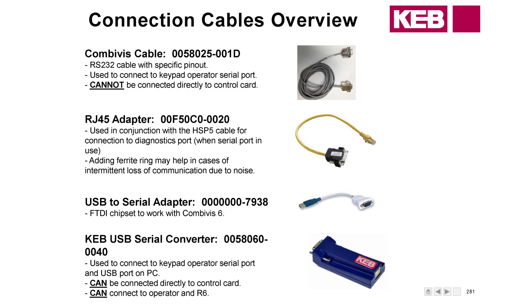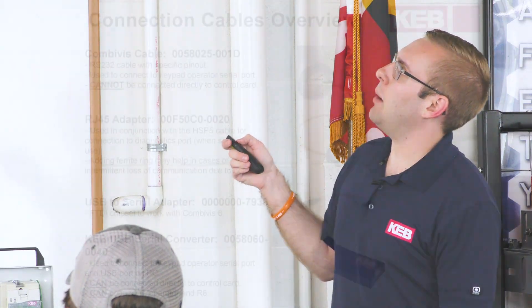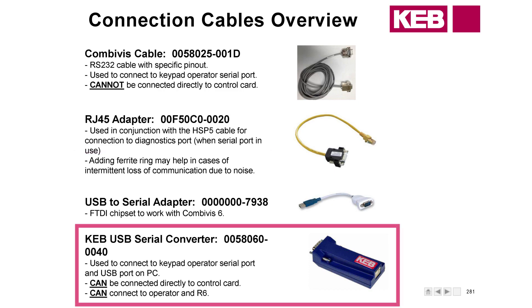The KEB converter can be connected directly to the control card and you can connect to the R6. Noise can affect the connection — you might be able to connect but drop your connection halfway through, or make parameter changes on the computer that don't make it to the drive. If that is the case, I recommend using a ferrite ring. For the most part though, I haven't seen too many issues with the KEB converter — these are what I prefer.